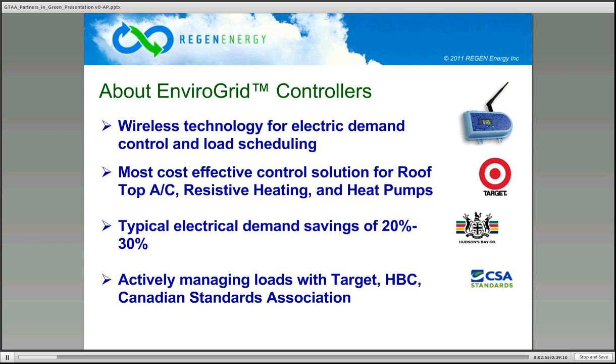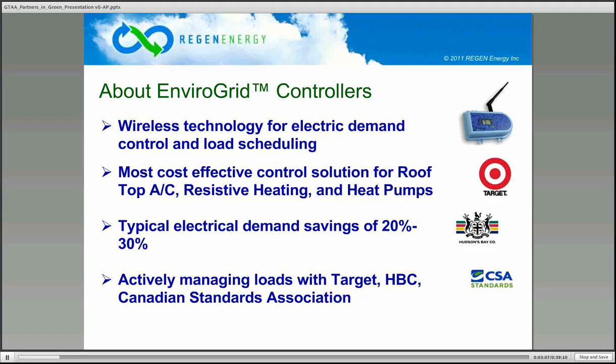We've also got some installed on resistive heating in a couple of locations, one of which is school portables, baseboard heating. Typically, demand savings are around 20%, 30% would be a little high, it can be done, in terms of saving of peak. When we model the stuff we put in our economic models, we put in a 15% reduction in peak, but we typically achieve closer to 20%, sometimes over.